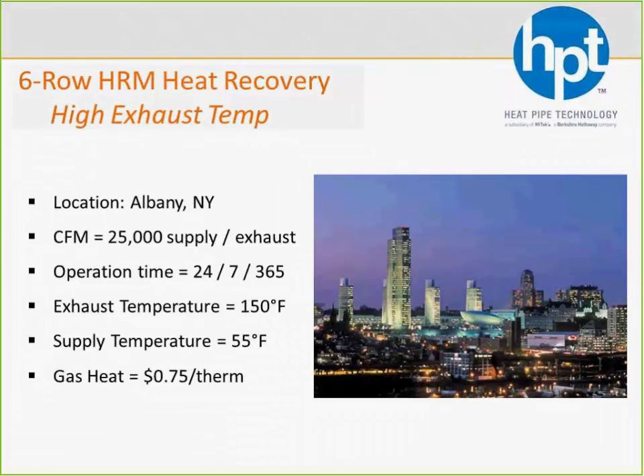So, a quick scenario. Again, you go and select our Select Plus software. You can run some bin analysis at all kinds of conditions. This is one I did for Albany, New York, just considering a 25,000 CFM system running 24/7 all year round. They're always exhausting 150-degree air, and they want to supply 55-degree air all the time. And for the bin analysis, I was told to use 75 cents a therm.